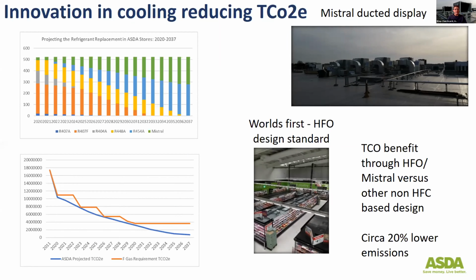The blue line in the bottom left-hand graph is actually showing our projected reduction, which clearly shows not only are we on track to meet that requirement, but certainly as we head to 2035, we'll be well below the F-gas regulatory standard.